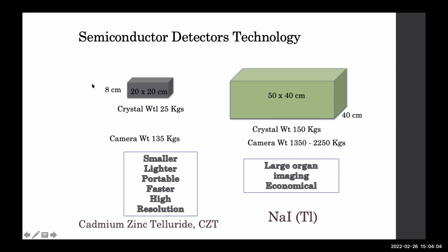Whereas the current generation gamma cameras which are coming, which are very costly, have detector systems which are very, very small, in the size of 20 by 20 centimeters. And they have very small crystals of a few millimeters, maybe 3 to 4 millimeter pixel size detectors. They are lighter, portable, with faster acquisition and high resolution.